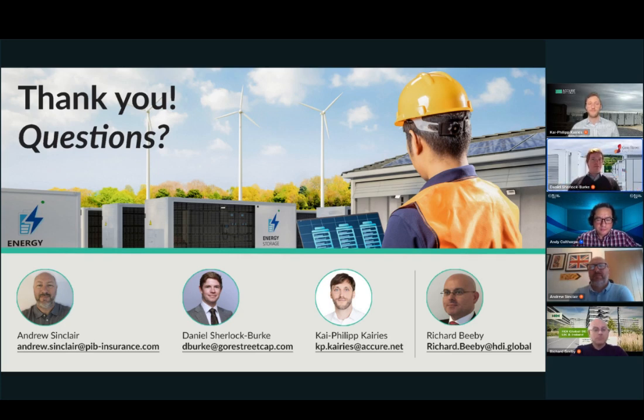From the analytics perspective and batteries, yes, it's ever changing - there's better products being brought on the market. But if you look at the most common cells installed over a few years, there haven't been huge amounts of changes there, so you can still use the same approaches. A lot of the modules still being installed today have been around for a couple of years now, so it's not like it's changing from site to site. The overall setup for every site should have its own hazard mitigation assessment, or something equivalent, where you look at the specific risks of the site - similar to how a fire risk assessment generally should be done site-specifically as well - and it should account for operating procedures around it.